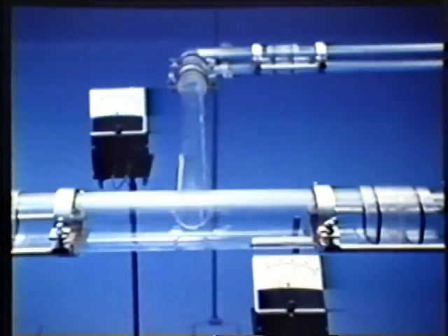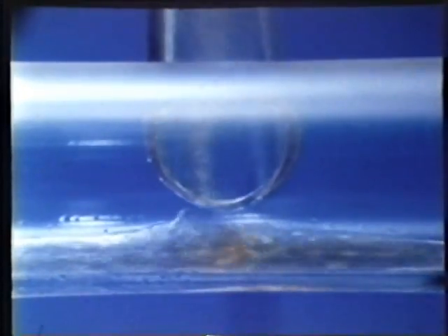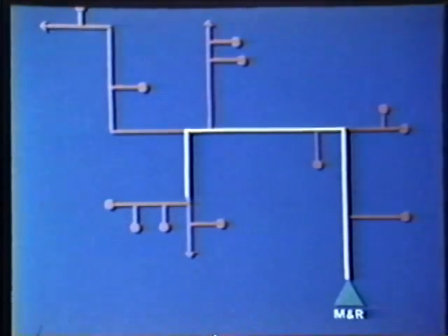In this particular model, the branch line is of smaller diameter than the straight line. If the gas stream divides into two equal parts, the liquid flow will in this case also take the branch line. When the gas stream through the branch line is reduced, all the liquid will at a given moment go straight on. Route preference also occurs with complete annular flow. It follows that any condensate formed at the beginning of a regional pipeline network will generally flow to a single terminal branch of that network. It is possible to calculate to what offtake points the condensate is likely to be carried, where appropriate measures can then be taken.